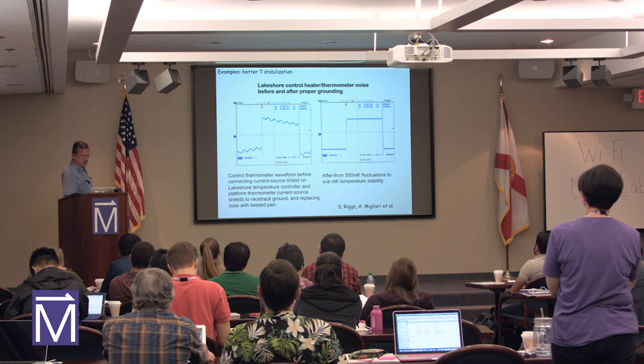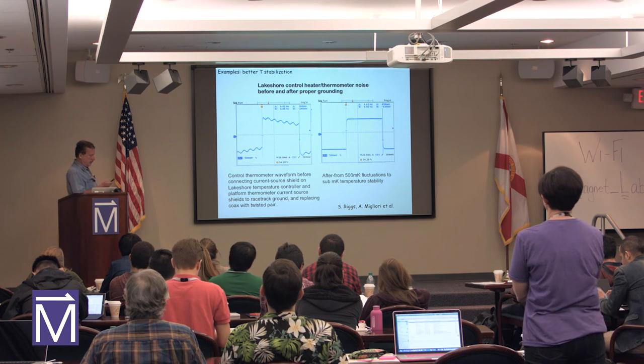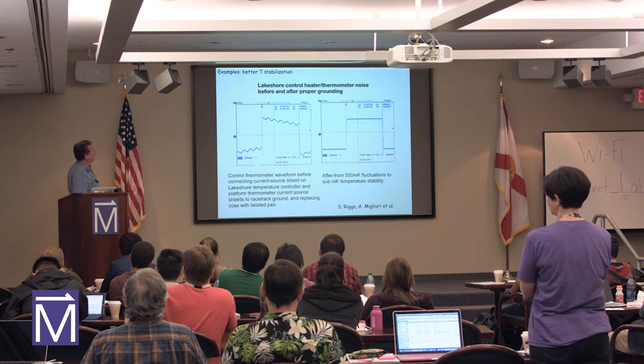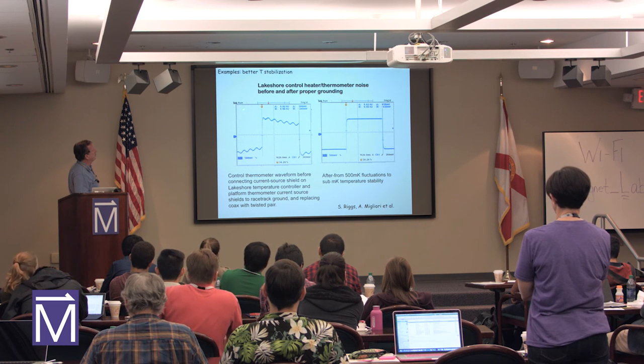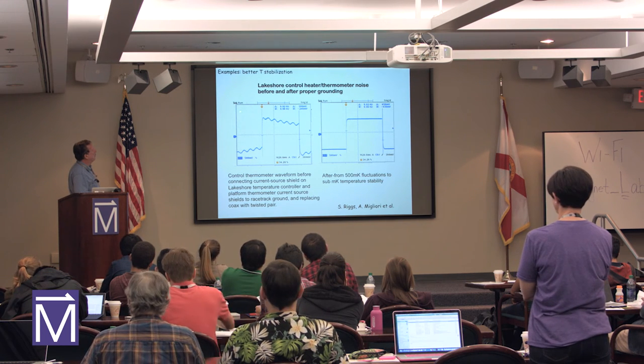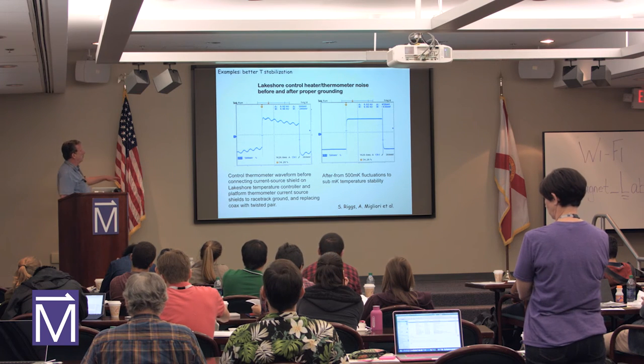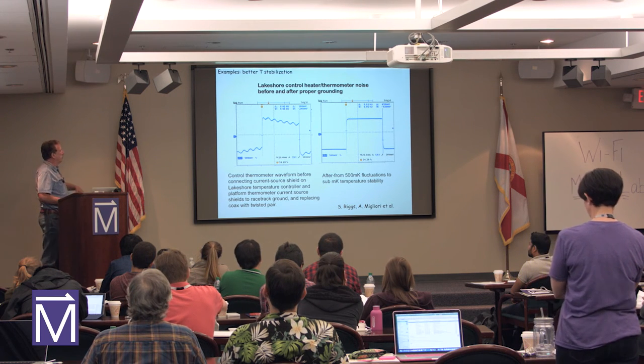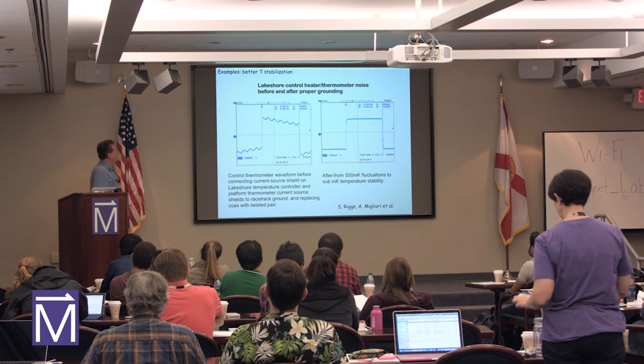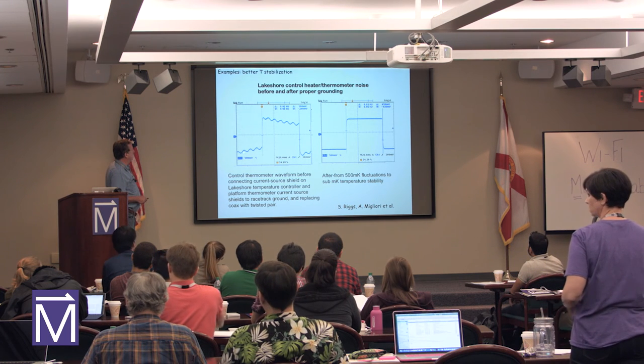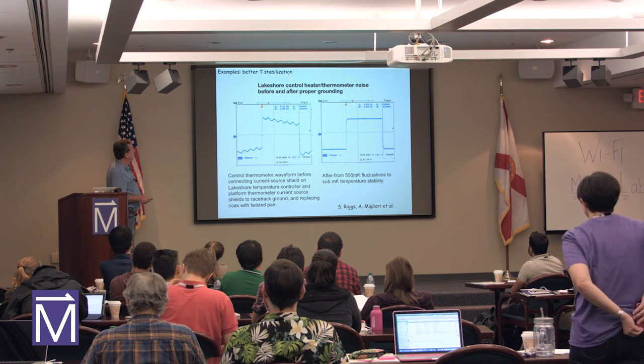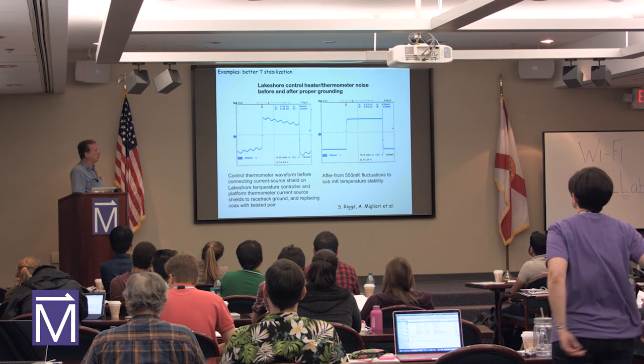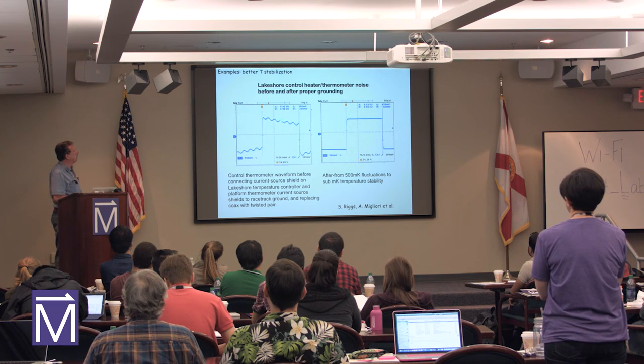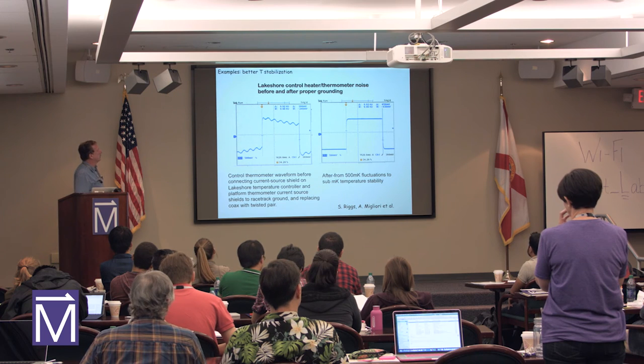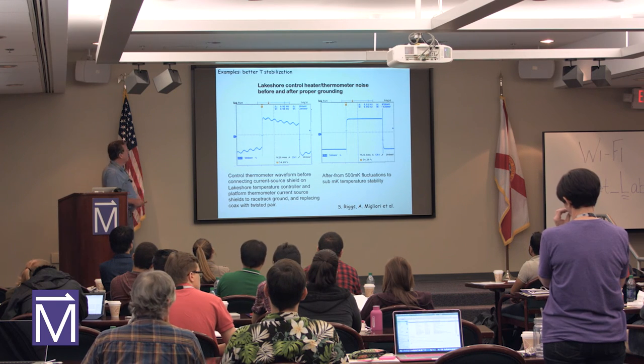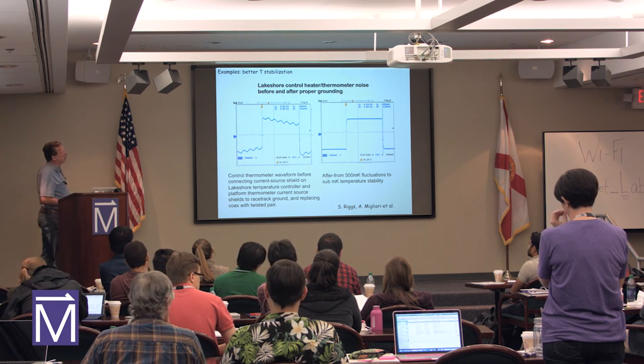So those are examples. This is a signal in a Lakeshore temperature controller. Lakeshore works this way: it puts a plus-minus wave to the thermometer and measures. But here, as you can see, what was modulated from low frequency, 60 hertz, is of the order of the measurement. This is how it looks after proper grounding.